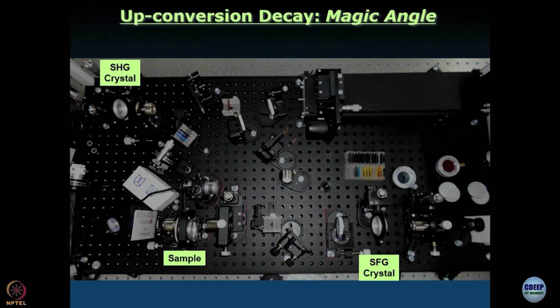To keep it very, very brief, generally you excite using a linearly polarized light, and you do that because first of all the laser that you use is usually linearly polarized. A Ti-sapphire laser is very nicely linearly polarized. If you are working with a diode laser, of course, you cannot work with a diode laser for upconversion. For TCSPC, a diode laser usually is elliptically polarized, which means there is a mixture of horizontal and vertical polarizations. There you put in another polarizer and generate one kind of polarization.